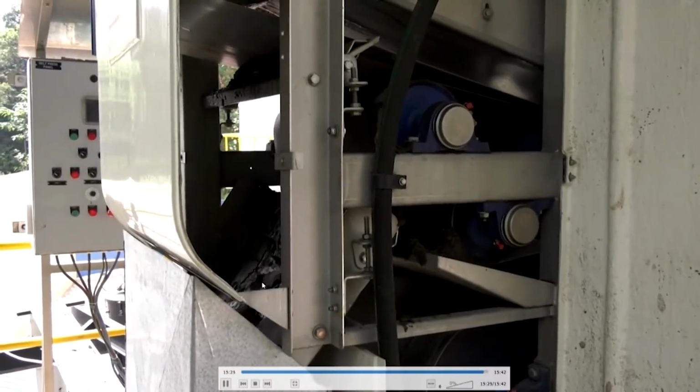Let's look at the filter cake. Here you can see the outlet. After dewatering, this is the sludge, the microbes. You can now see the dewatered sludge coming out of the filter press. Now the volume is less, and because I removed the water, the mass is less, so it's relatively easy for me to transport and then treat this. Typically it would go to anaerobic digestion, but because it's a small plant in IIT Roorkee, anaerobic digestion is not really required.